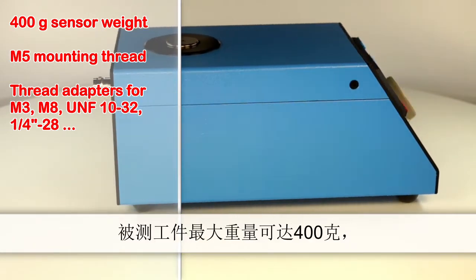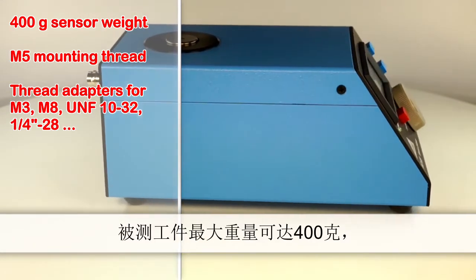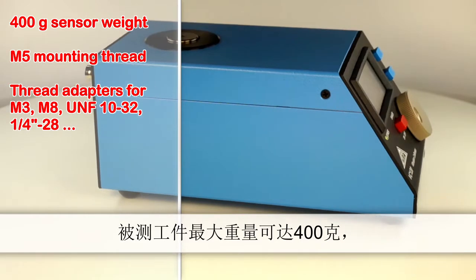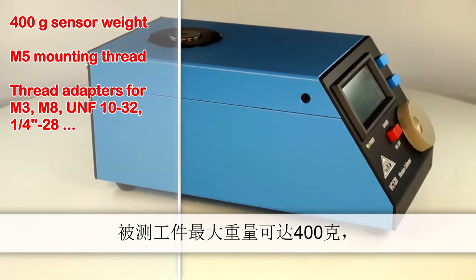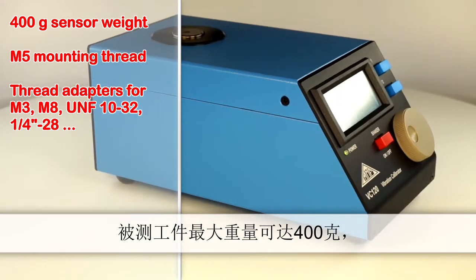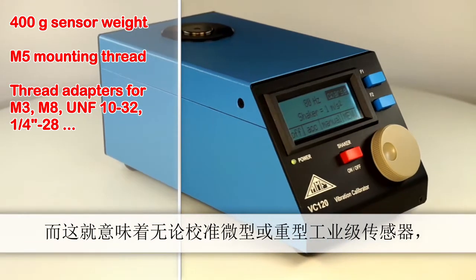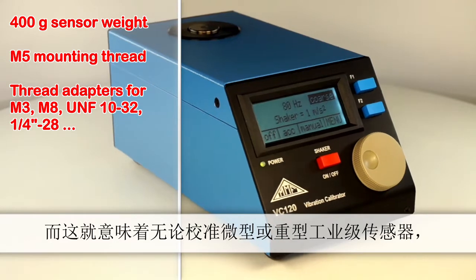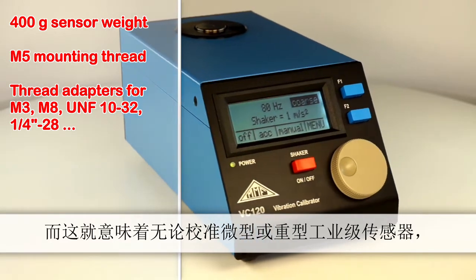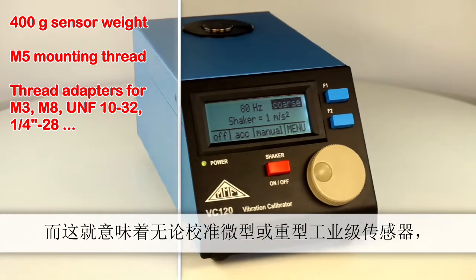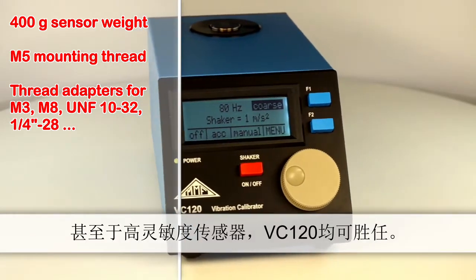The test object can weigh up to a maximum of 400 grams. This means you can calibrate lighter sensors as well as heavier industrial types or high sensitivity sensors.